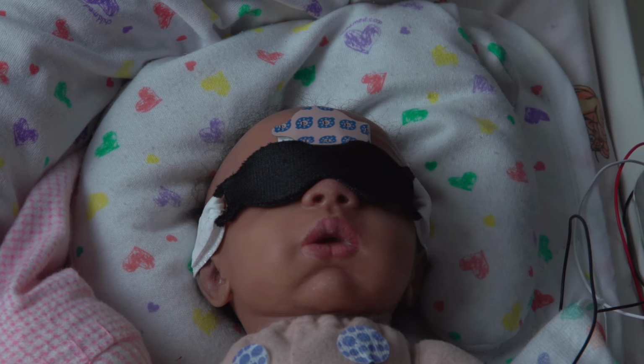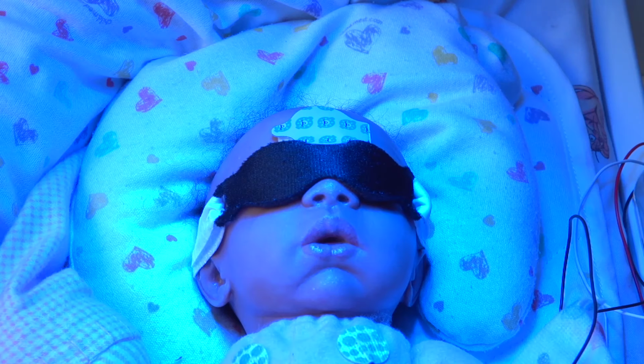Although it is unlikely that light will penetrate the sides, any light that does reach the skin could affect future Bilichek measurements. Continue or discontinue phototherapy as indicated by the latest measurement. Leave BiliEclipse on the skin until no further Bilichek measurements are needed. This ensures that future measurements are made from the same protected location.